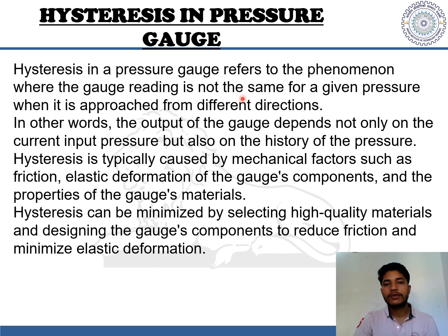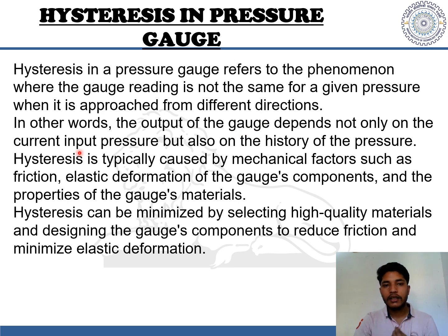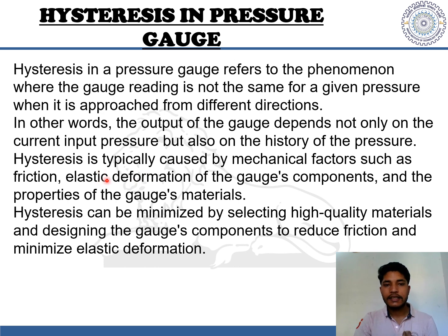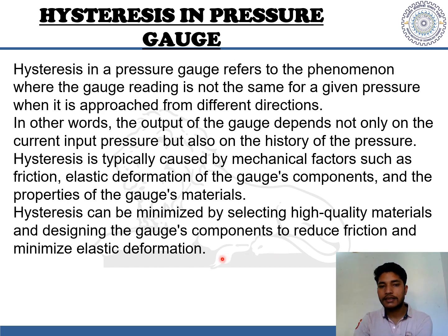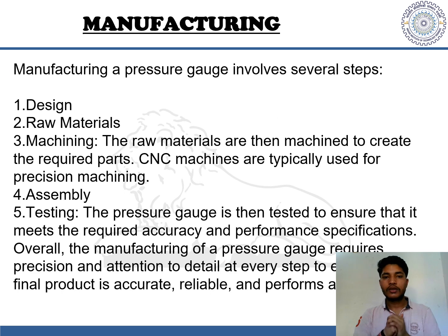Now let's look at hysteresis. Hysteresis in a pressure gauge refers to the phenomenon where the gauge reading is not the same for a given pressure when it is approached from different directions. In other words, the output depends not only on the current input pressure but also on the history of the pressure. Hysteresis is typically caused by mechanical factors such as friction, elastic deformation of gauge components, and the properties of the gauge's materials. It can be minimized by selecting high-quality materials and designing components to reduce friction and elastic deformation.